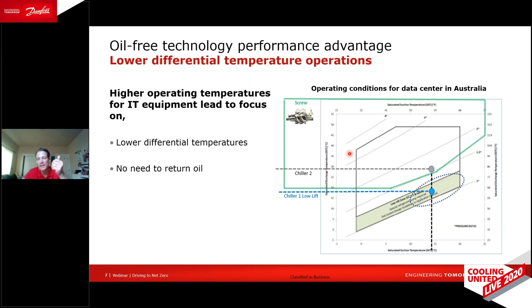That's why you see, whether it's with our technology or those of others, that oil-free technology has become so prevalent in data centers today, because they are lowering that heat rejection temperature and increasing that cooling temperature, and therefore operating at the lower differential, and therefore this technology is a perfect fit to optimize the efficiency for it.